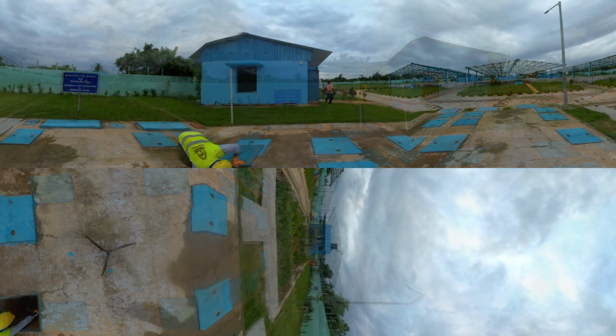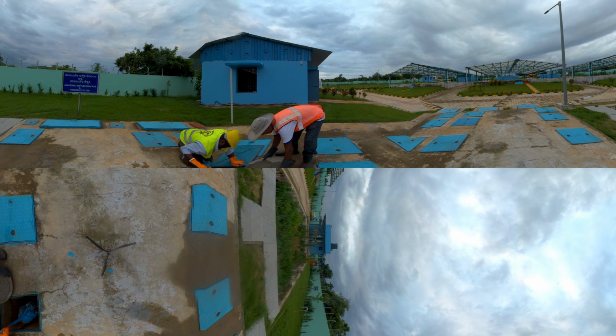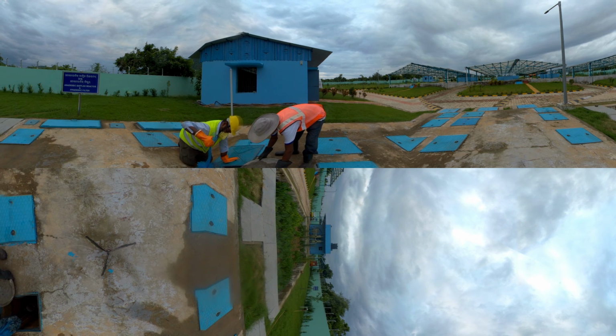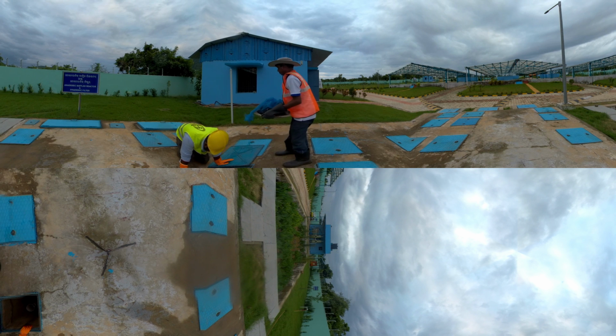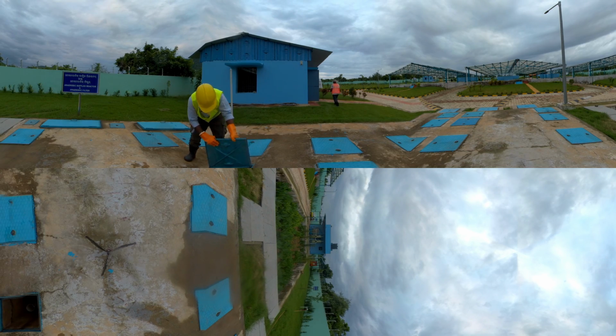The filter media should be cleaned once in every 5 years. To do so, pour water with force over the filter materials using a pump. The clear water collected in the filter chamber should be removed through the desludge outlet pipe. During this time, you should check the condition of the tank for wear and tear, such as plastering, condition of the perforated slab, pipes, etc.